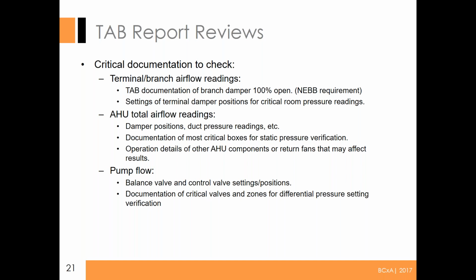During the tab conference, it's a good time to tell them what you'll be looking for in the report and the readings you want to see. If they're NEBB, they're required to show in the report what branch damper is at 100% open, things like that, because they often don't do it. They'll probably do anything you ask if they only have to do it once, but people start complaining if you send it in and then start editing. So the more you tell them upfront, like that I'll be checking that you've got the most critical boxes for static pressure verification shown, the more likely they'll do it.